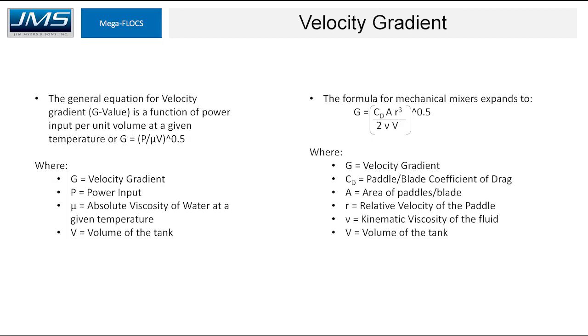We'll begin with velocity gradient, which is a measure of mixing intensity. The general equation for velocity gradient, or G-value, is a function of power input per unit volume at a given temperature. The gradient is dependent on power input, temperature of the water, and volume of the water you're mixing.